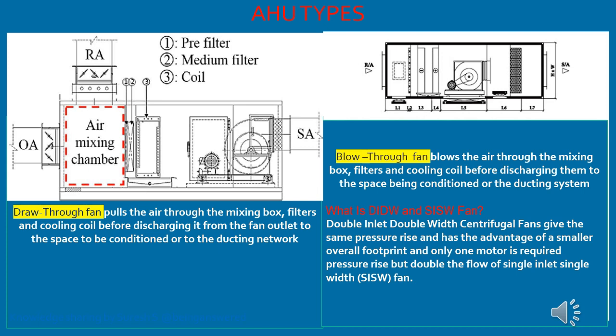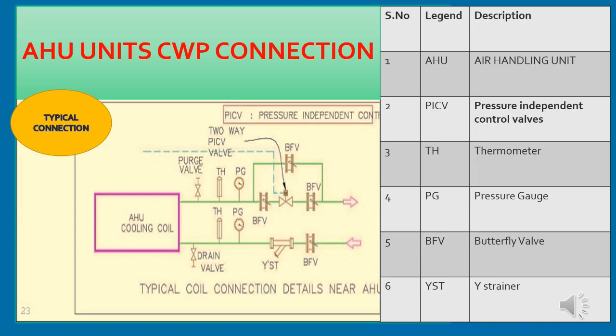What is DIDW and SISW fan? A double inlet double width (DIDW) centrifugal fan gives the same pressure rise and has the advantage of a smaller overall footprint, requiring only one motor, but delivers double the flow compared to a single inlet single width (SISW) fan. We have now seen the AHU specifications and the two different types of AHU fans.